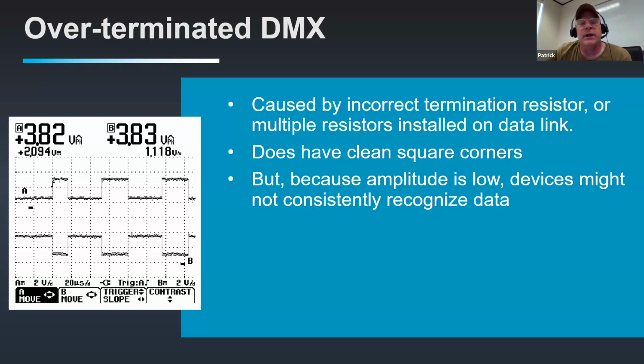Opto splitters are probably what I see and hear about the most nowadays, because each opto splitter has its own self-terminator. There are a lot of lighting fixtures out there that do self-termination. It's a mechanical connection, so if the cable is inserted on the output side, it pushes the terminator back. It's possible that the terminator can be left back, meaning it mechanically doesn't pop back to unterminate, and you can over terminate inadvertently that way.